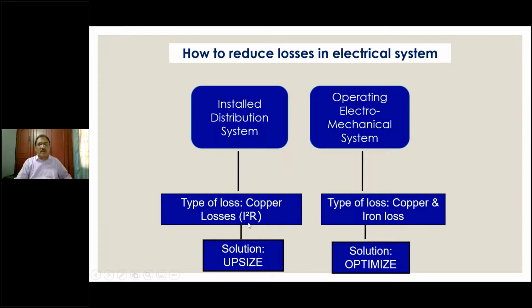which you can't do. You will become unpopular. So what you can do is always reduce the R. How do you reduce R? Resistance is reduced by upsizing the conductors. So a simple rule of thumb for the installed system to reduce I square R losses is to upsize the conductors or increase the number of runs. I have one slide on this, not more, but I will try and bring out that information. The operating electromechanical system has losses in both copper and iron, typically in motors. As per theory, the best efficiency occurs where the copper and iron losses meet. Therefore, you must remain as close as possible to the optimum level, and optimization is the solution available to reduce your copper and iron losses. Simple rule of thumb, nothing difficult to understand or fret about.